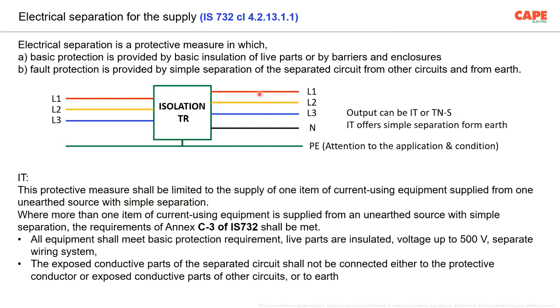The electrical separation is first of all recommended for one current using equipment. One example is the inverter of solar PV, or say for example a UPS, because the rectifier part of the UPS is unable to withstand some voltage because it has got sensitive electronics. You make an electrical separation. As a result, you ensure that your equipment is able to withstand it. When more than one item of current using equipment is supplied from an unearthed source, a simple separation, the requirement of Annexure C of IS 732 shall be met.